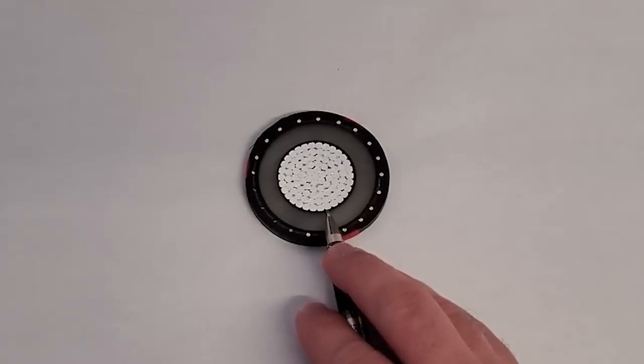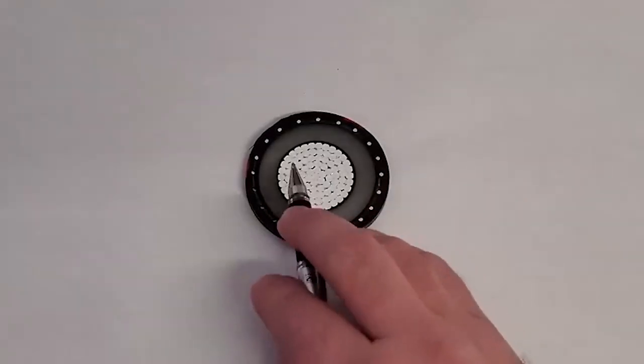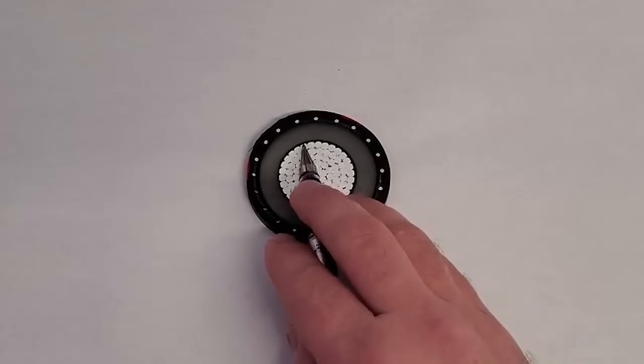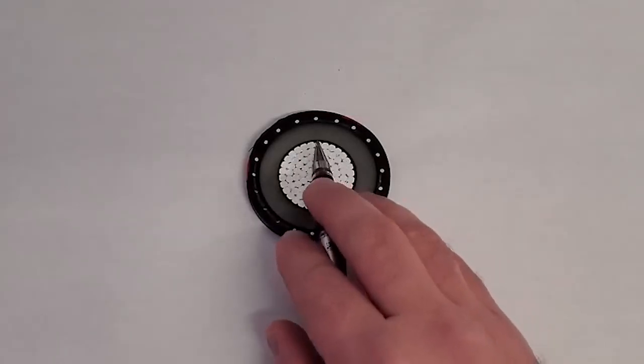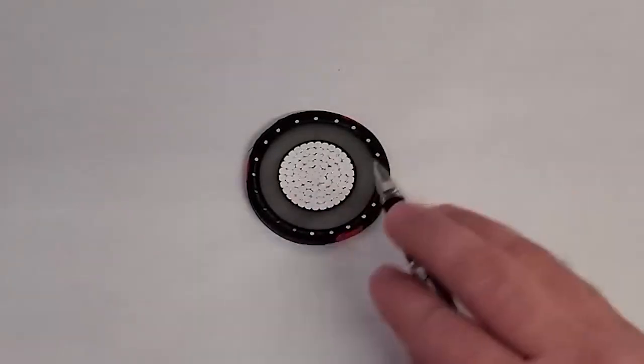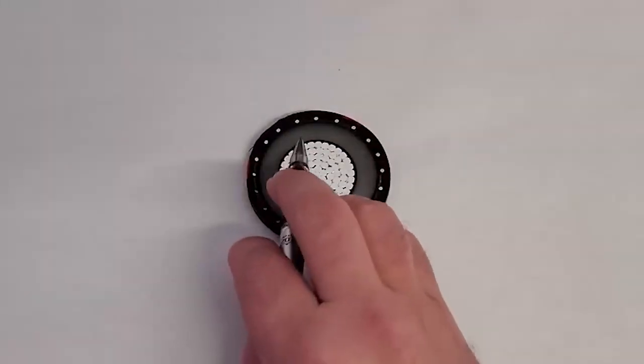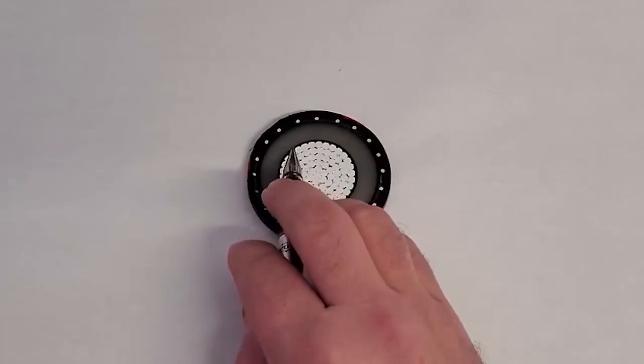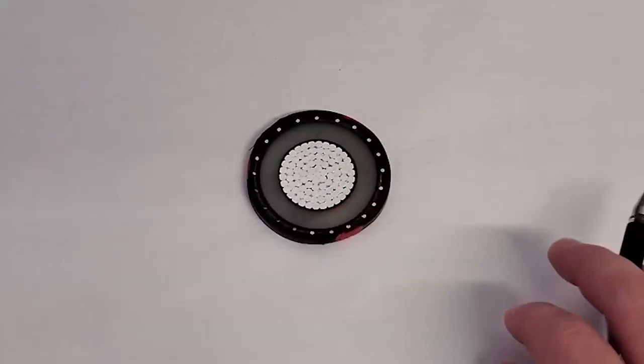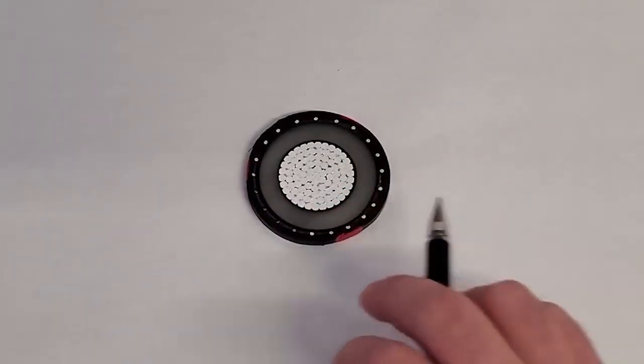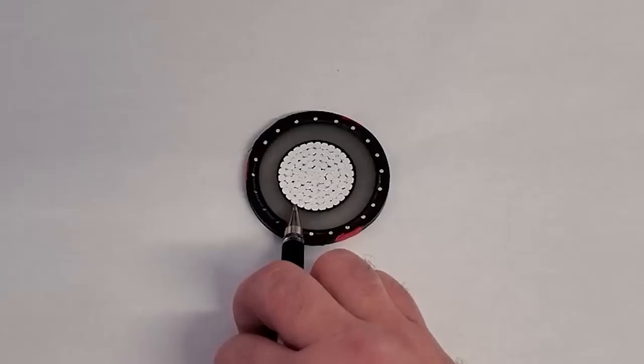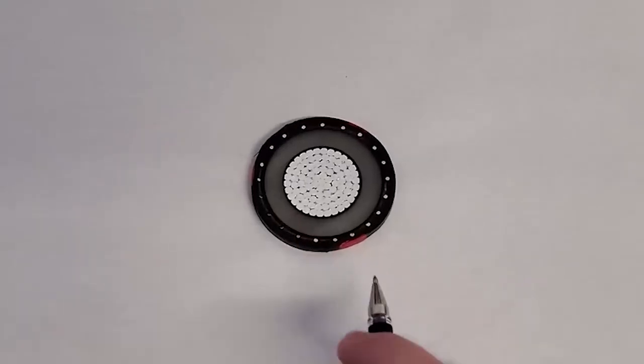The purpose of that is to try to even out the lines of flux. So there's inefficiencies here in the edge of the cable, and you have a lot of flux coming off of this, wanting to head to ground. And you may have more in one area than you will the other, because this isn't a perfectly round, symmetrical cable. So the purpose of that is to take some of that flux out and begin to sort of even it out. Why do we want it evened out? That's what we'll talk about next.